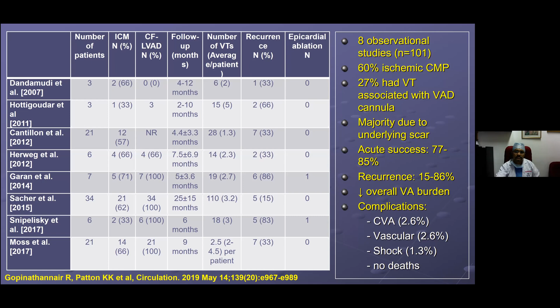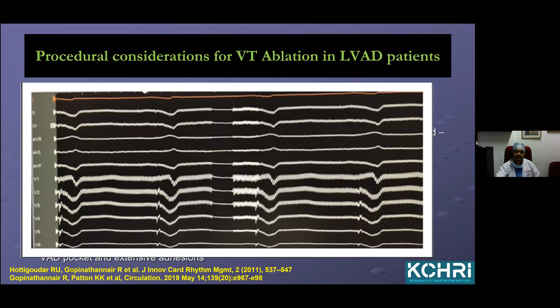We already talked a little bit about that, and we talked about HeartMate 3 and the noise issue. So this is an example of that surface ECG noise from HeartMate 3. You can see that every 2 seconds it clears up, and this can be mitigated to some extent by adjusting the low pass filter in the mapping system, but it's impossible to completely get rid of. But when you adjust the low pass filter, you also risk not picking up some things.